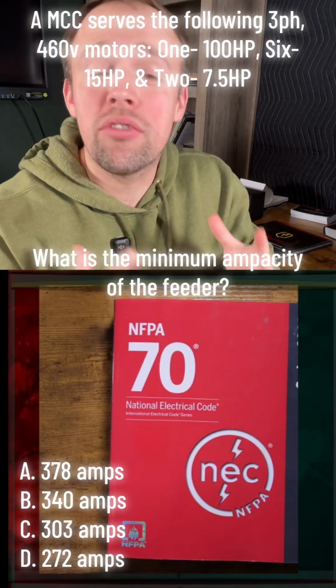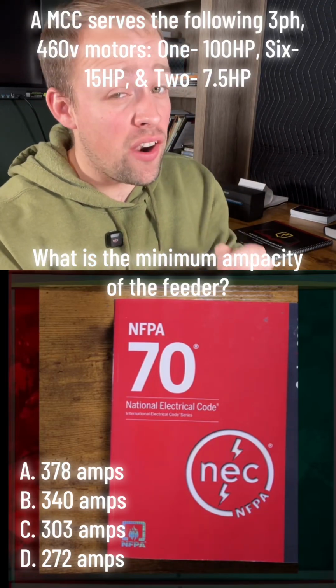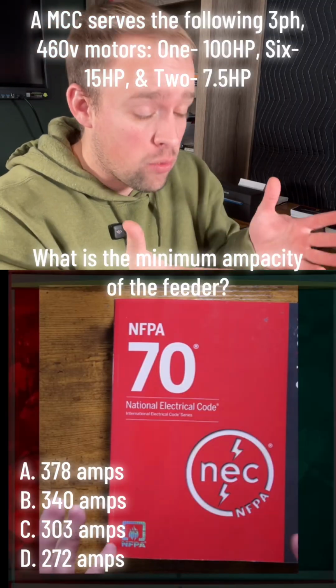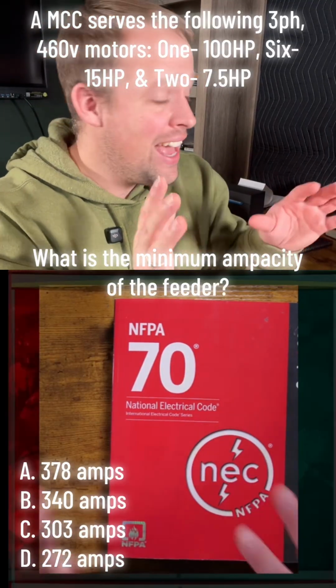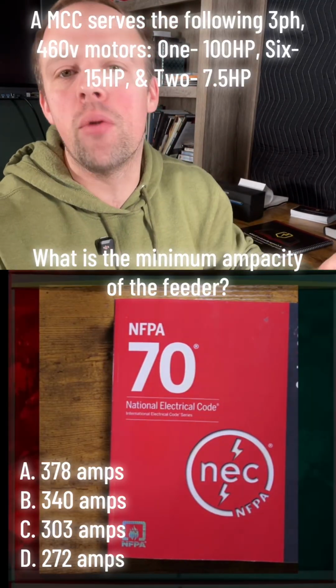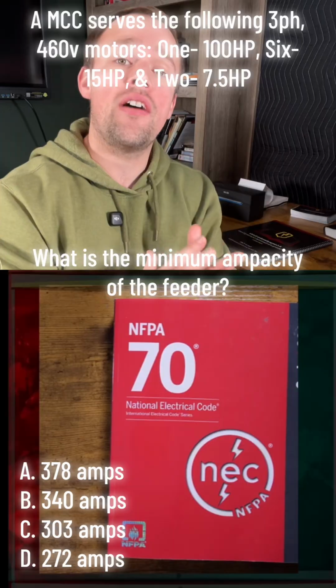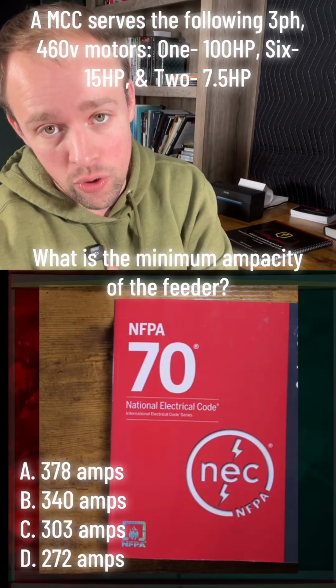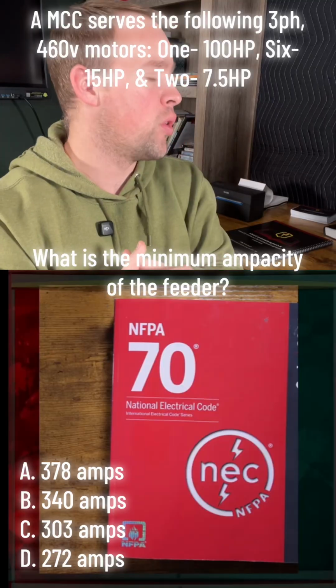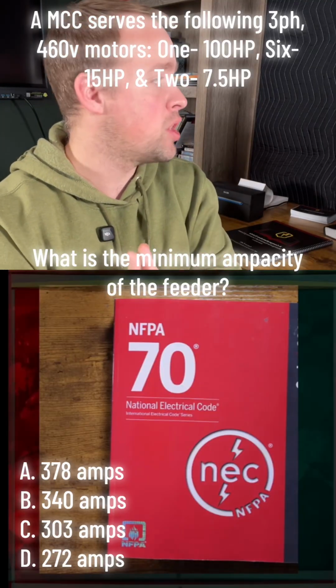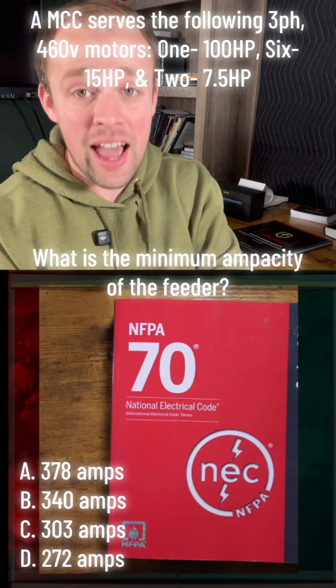Electricians, I'm going to walk you through a licensing exam question that you very well might see on your licensing exam. Again, walking you through using the 2026 NEC. Our question reads, a motor control center serves the following three-phase 460-volt motors. We have one 100 horsepower motor, six 15 horsepower motors, and two 7.5 horsepower motors.